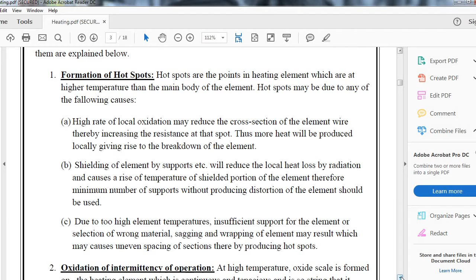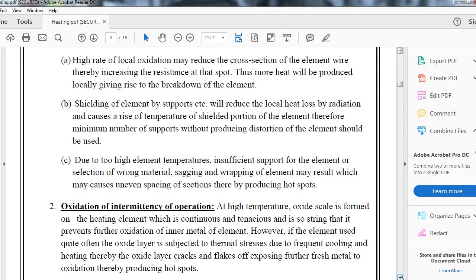The other reason for failure is oxidization and intermittency of operation. At higher temperature, an oxide scale is formed on the heating element, which is continuous and tenacious. It is so strong that it prevents further oxidization of the inner metal of the element. However, if the element is used intermittently, the oxide layer is subject to thermal stress due to frequent cooling and heating. Thereby the oxide layer cracks and flakes off, exposing further fresh metal to oxidation, thereby producing a hot spot.